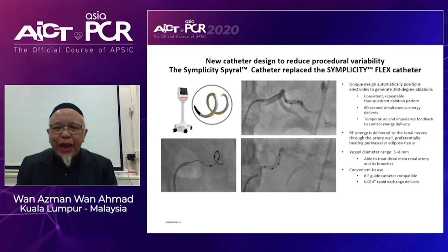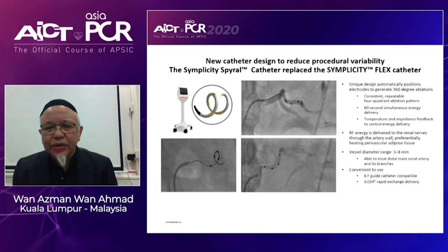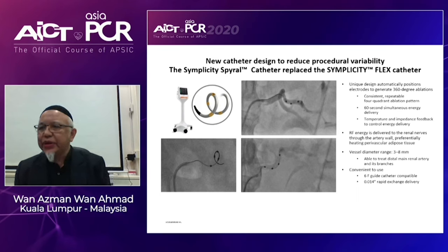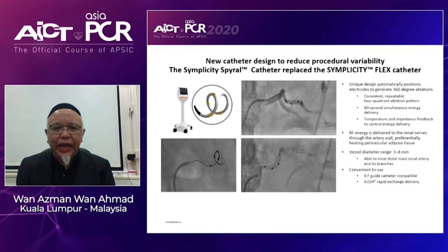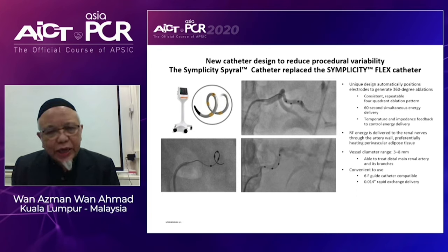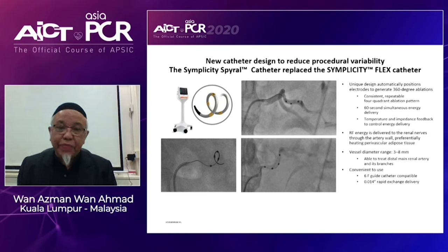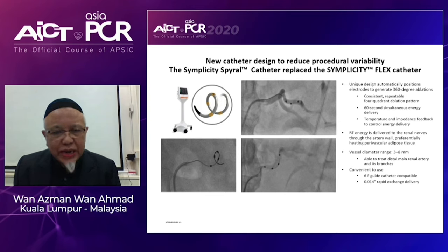Comparing the first generation renal denervation catheter — the Flex catheter — with the second generation Spyral catheter, there are significant improvements. The Spyral catheter has a unique design that is automatically positioned to generate 360-degree ablation in a consistent, repeatable four-quadrant pattern, and requires only about 60 seconds to perform renal denervation compared to two minutes with the previous catheter. With just one catheter you can treat vessels between 3 to 8 mm — the main branch and side branch of the renal artery. It requires only a six French guide and is compatible with a 0.014 wire system.